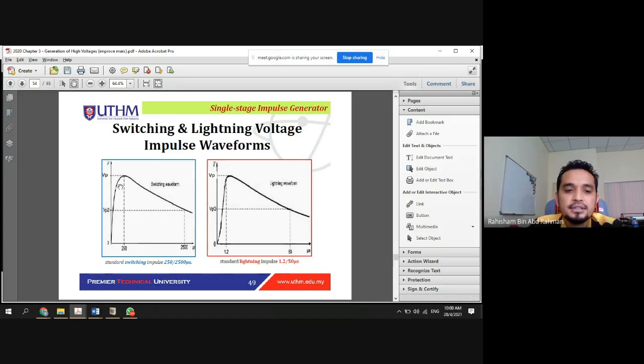The 250 is the rising time, meaning the time to reach peak. The 2500 microsecond is from the peak to 50% of the peak value - not to zero, just 50% of the magnitude. Say this is 100 kV at peak, then 50% will be 50 kV. So we count from the time to reach peak to the decay reaching 50 kV. This is normally in the range of 2500.